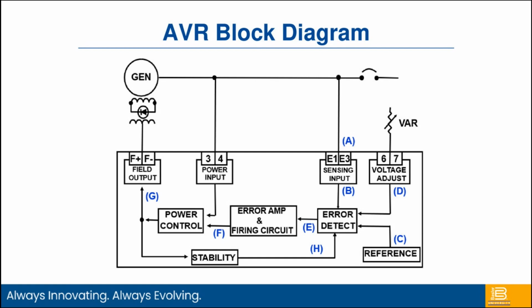What happens is the sensing input gets compared to the sum of the references, be that external adjust and the reference point, so D and C, and we create some type of error signal. Throughout circuitry, we take that error signal and we amplify it. That amplified error signal then gets put into the output circuit. The output circuit takes the power input at terminals 3 and 4 and feeds it into our power control. Then we use the output of our firing circuit. Circuitry internal is going to put the DC output into the field through terminals F plus and F minus. It's going to create flux on the rotor, increase or decrease the amount of flux on the rotor, and increase or decrease the amount of voltage out of the machine.